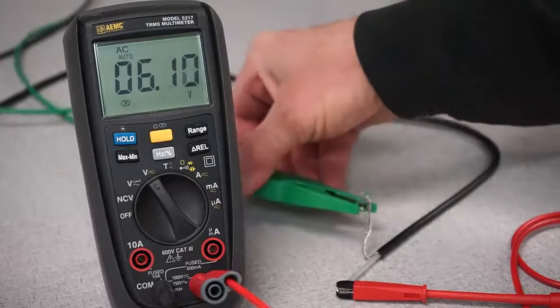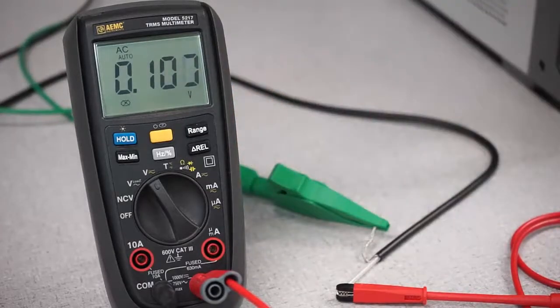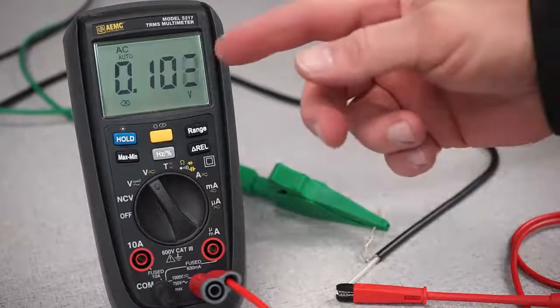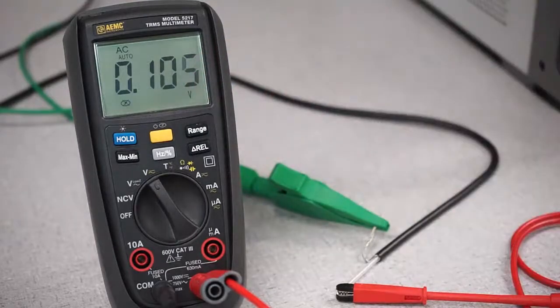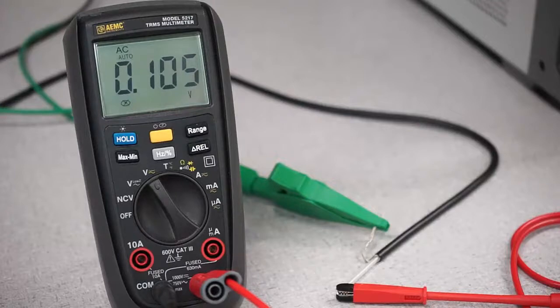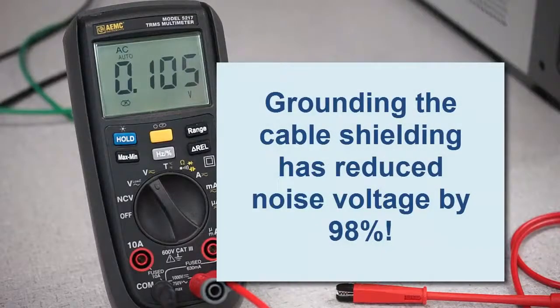Now we'll connect the cable shielding to the ground. Notice that the noise voltage has dropped to around 100 millivolts, nearly two orders of magnitude lower than our previous reading. In other words, grounding the shielding has reduced noise voltage within the cable by around 98%.